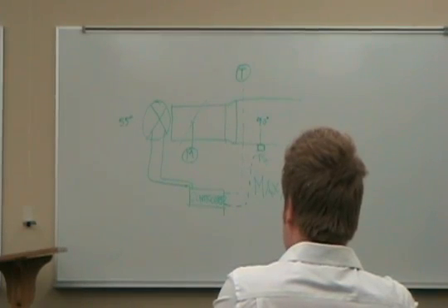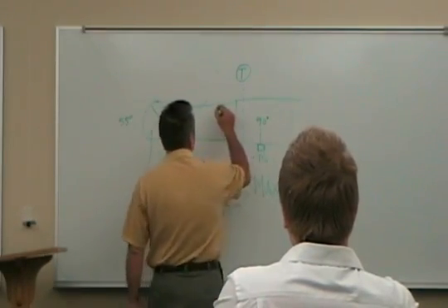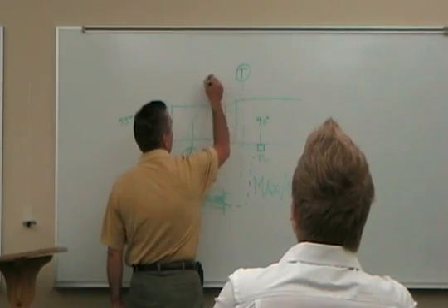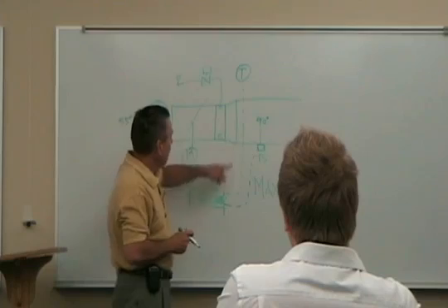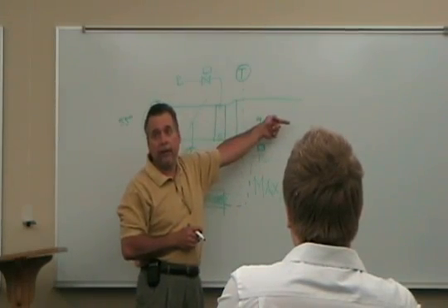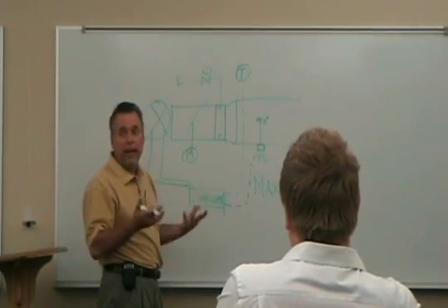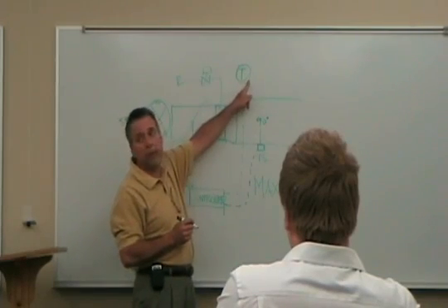So if I've got the same thing over here, 100 CFM max, 100 CFM minimum, so what happens is I've got a coil right here, whether it's a water coil or an electric coil. So what happens is I've overshot my temperature, thermostat's telling the controller the space is satisfied, the controller goes to the minimum airflow. But it's still pumping 100 CFM at 55 degree air through there. So the controller then, its response back from the thermostat says, the temperature is continuing to drop, I need heat. Damper's at its minimum position and the valve starts to crack open to maintain temperature in the space.